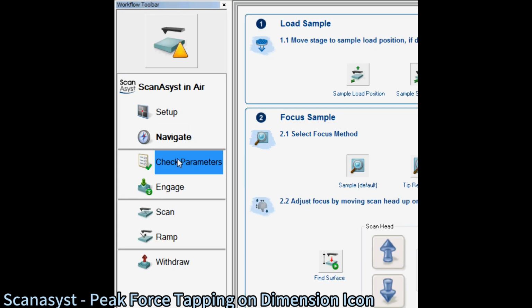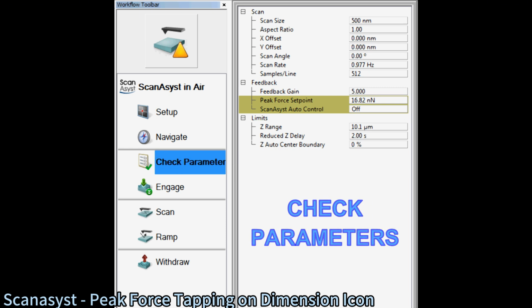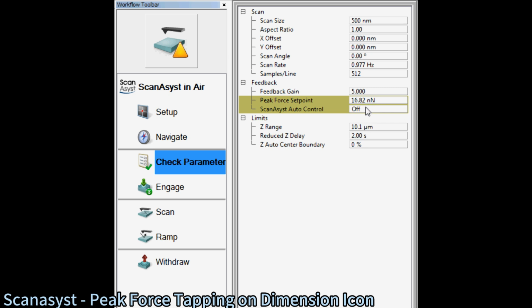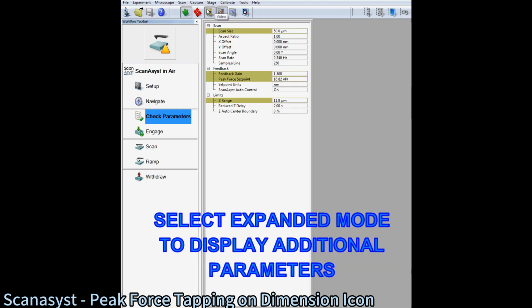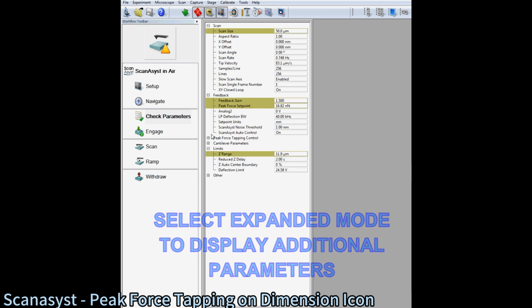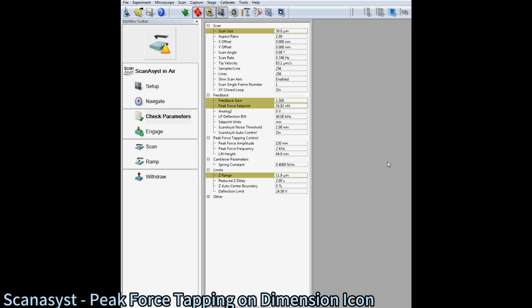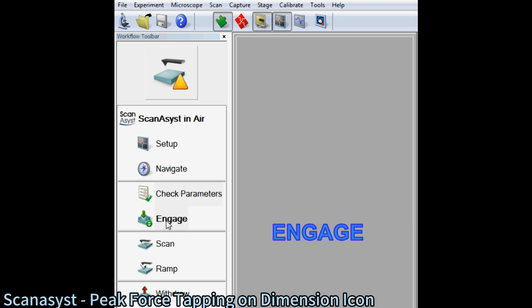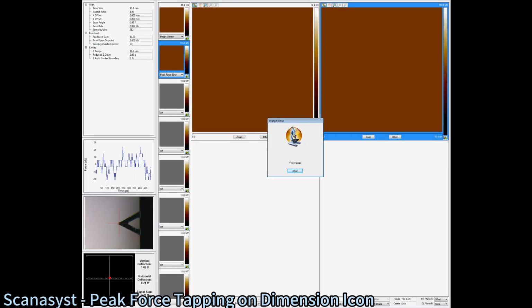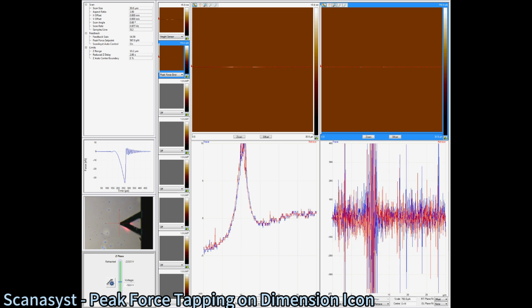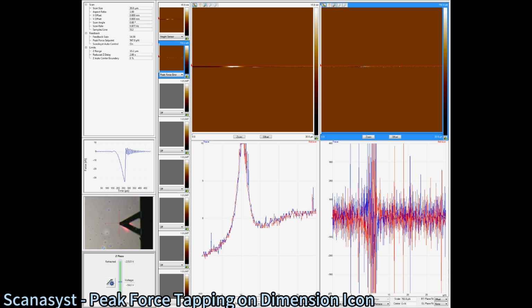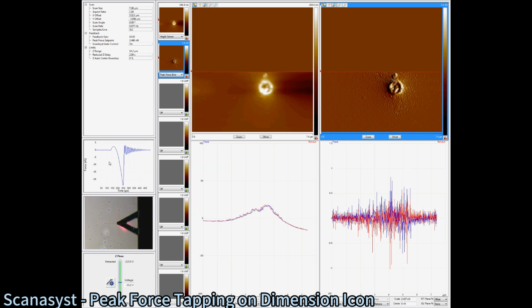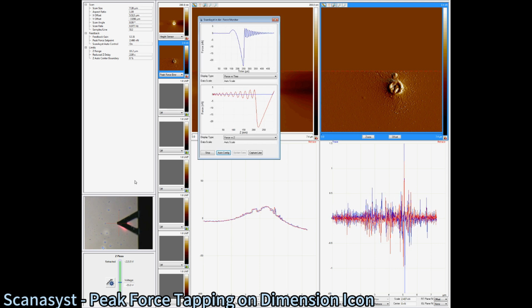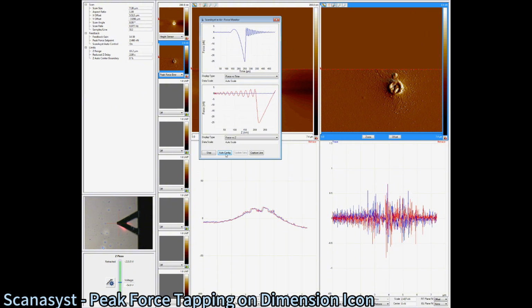Click the Check Parameters button to display the parameters list. Typical values are shown here. Make sure that ScanAsyst Auto Control is set to On before initiating the engage cycle. Select the Expanded Mode option if you want to display additional scan parameters. Initiate the Engage command and allow the probe to approach the sample and enter feedback. Monitor the trace signals from the data channels for indications of good topographic data or feedback from the sample. Undock the Force Monitor window from the control panel and adjust the data scale values as needed to observe a sufficient range of the force plots.